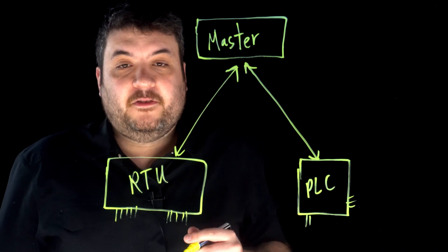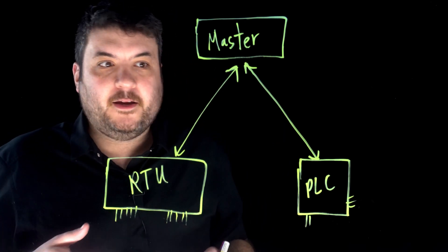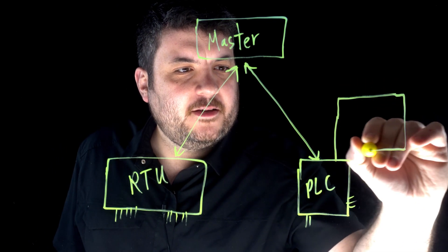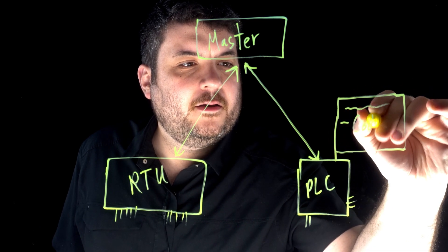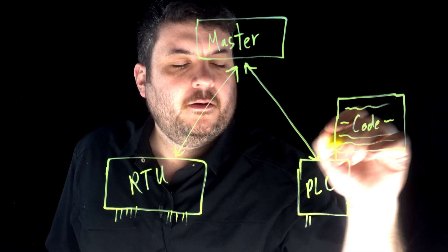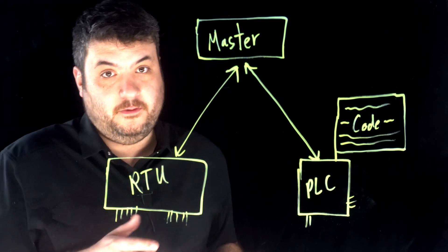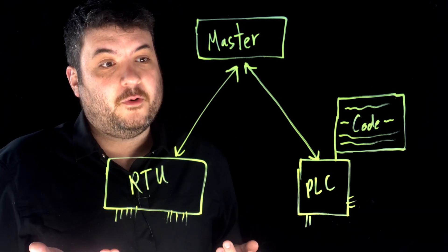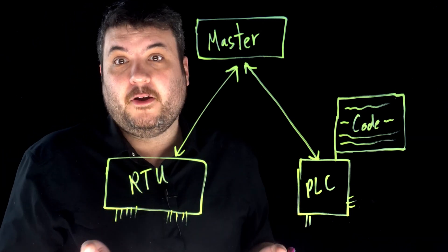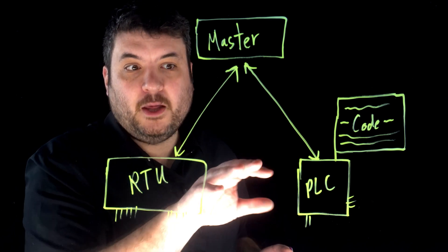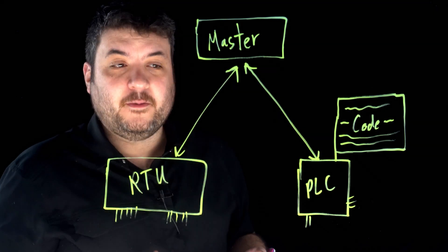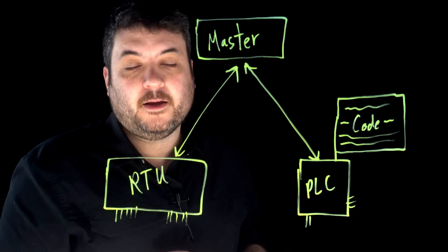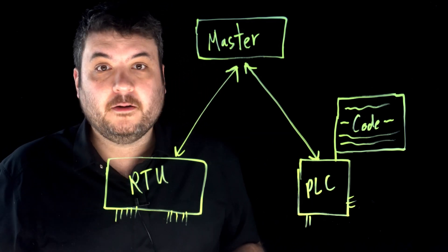Probably one of the key distinctions from a system design perspective — as you plan staffing, training, and building your team — is that with PLCs, you tend to have to write programming code into them. That can be awesome if you know what you're signing up for. You're writing code, so it's up to you to write it well, and you have to build all the functions you want. You can do some very advanced logic and it can be very powerful. But just understand what you're doing: you're playing the role of your own engineer. You've bought hardware that will host it, but you might be writing the code yourself or paying a consultant to do it for you.